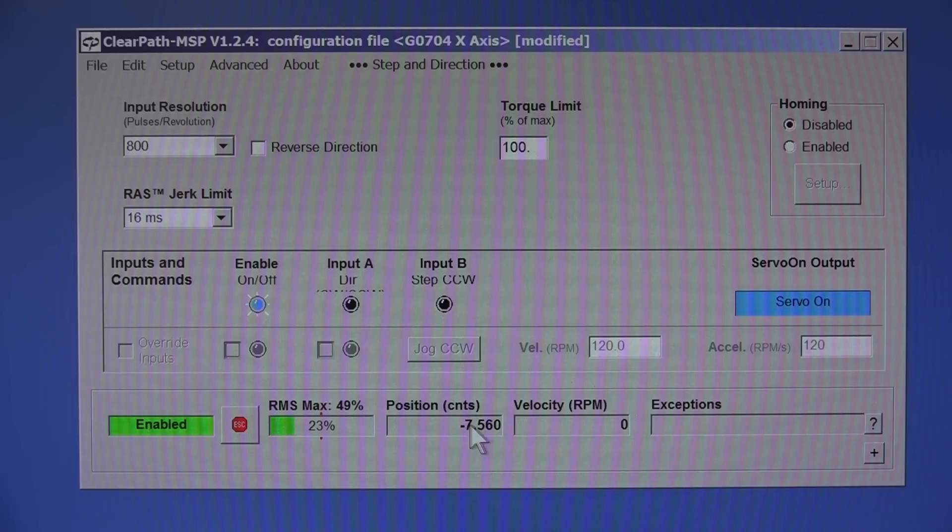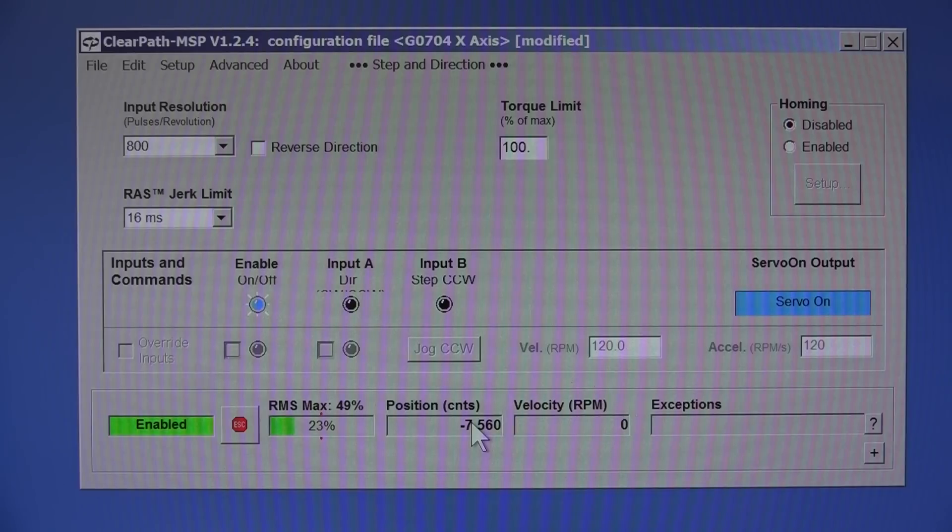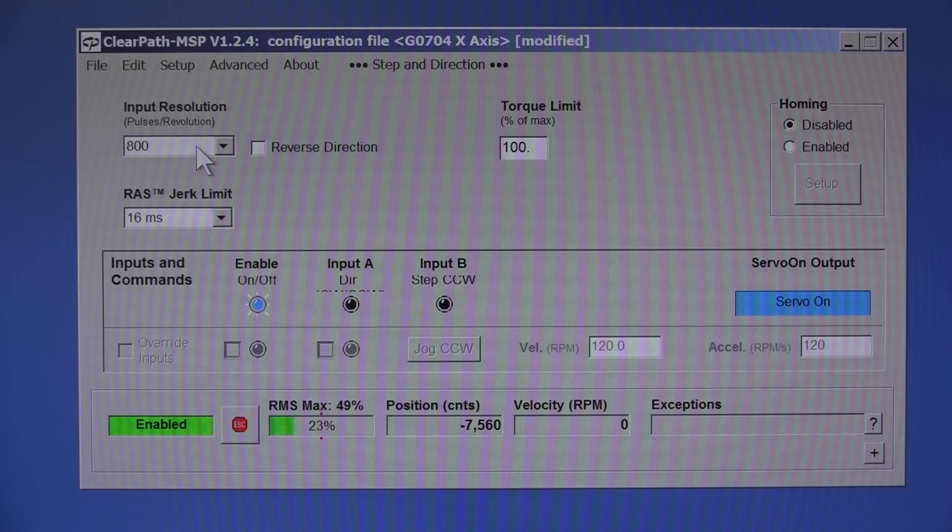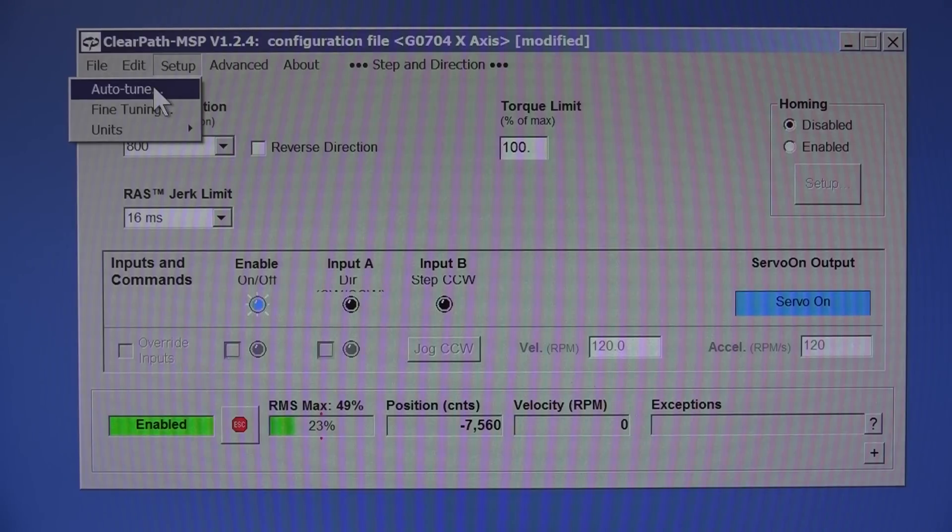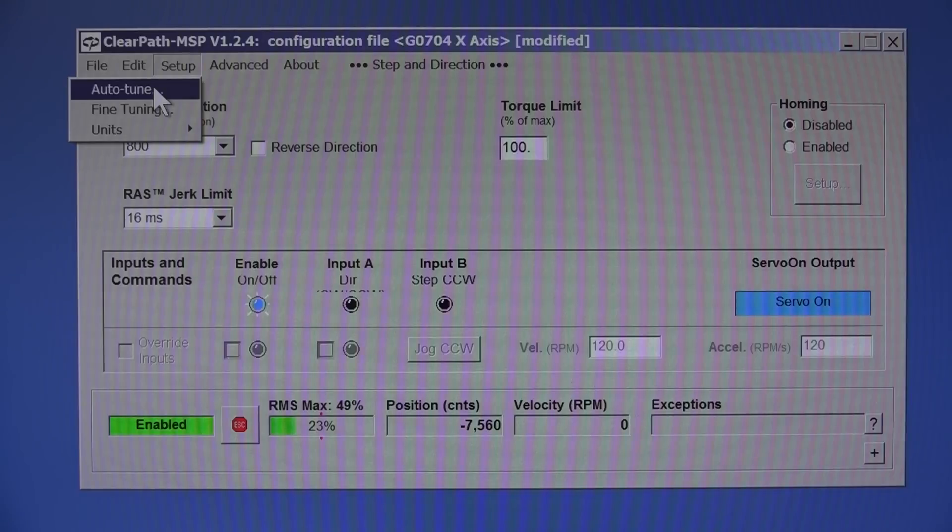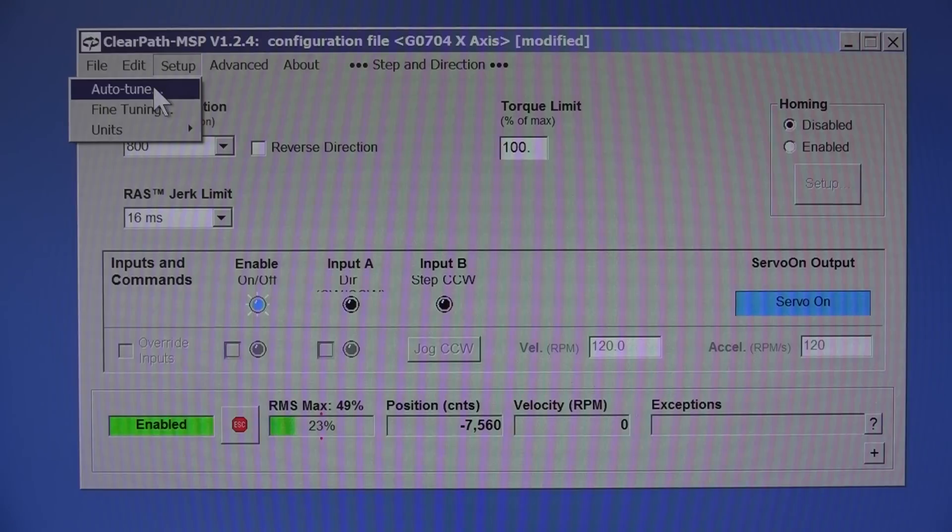The motor is enabled, any exceptions or faults pop up here. It keeps track of its count, so you can configure these motors so that they'll just move from one position to another without any kind of controller other than what's built into them. You can set the maximum torque up here and I've got it set at 100%, and you can set the pulses per revolution. Under setup there's this auto-tune function, and what you do is you move it manually back and forth maybe 20, 30 turns, then you say go.